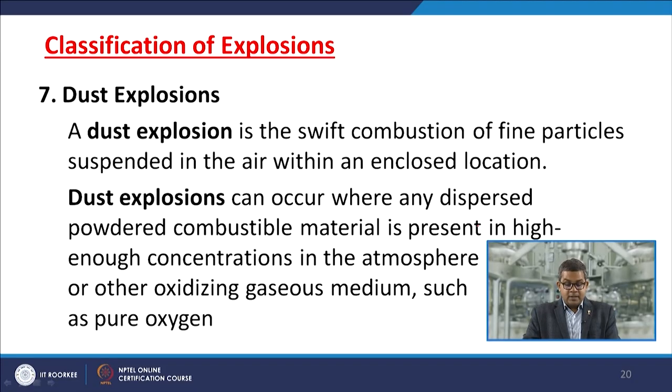Next is dust explosion. Dust explosion is a swift combustion of fine particles suspended in air within an enclosed location. Dust explosion can occur where any dispersed powdered combustible material is present in high enough concentrations in the atmosphere or other oxidizing gaseous medium such as pure oxygen. Again, it is very important, and there are many accidents in history that took place just because of this dust explosion.